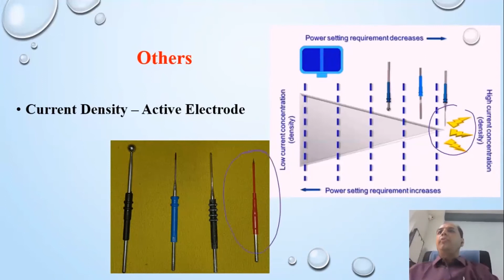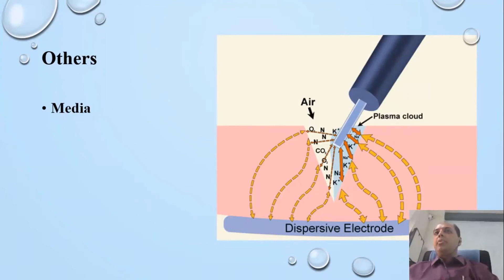The electrical properties of the media, air, water and saline etc. around the active electrode are included in the electrical circuit, especially if the electrode is held off the tissue, that is, near contact. Consequently, the impedance in a steam envelope or plasma cloud or ionized gas is much lower than that of air. This will increase current density. But saline or blood around the active electrode can make it function like a dispersive electrode, thereby decreasing power density. So, saline or blood must be soaked if we want to improve performance.